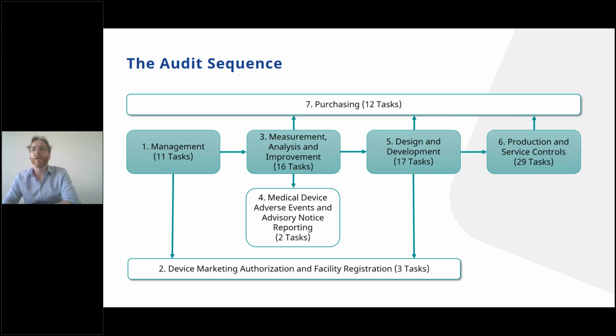And as I mentioned before, the audit duration is calculated according to the number of tasks that have to be audited. So you can see, for example, for management, we have 11 tasks. And if you look at production and service controls, we have 29 tasks. And depending on whether the company uses sterilization techniques, if it has high-risk products or not, if there are implants or not, and also on the amount of jurisdictions that are part of the program, we have more or less tasks, and as a consequence, we have a higher or lower audit duration.